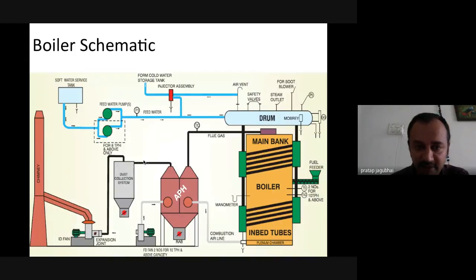So if we go into more specific detail, this is your water cycle. The purpose of the water cycle is always to ensure the water pressure is above the steam pressure, so that the boiler should not starve in water demand. So there is always water available to convert into steam. And the TDS is removed through the blowdown. That is the purpose of the water cycle, and to deliver the steam from the steam drum.